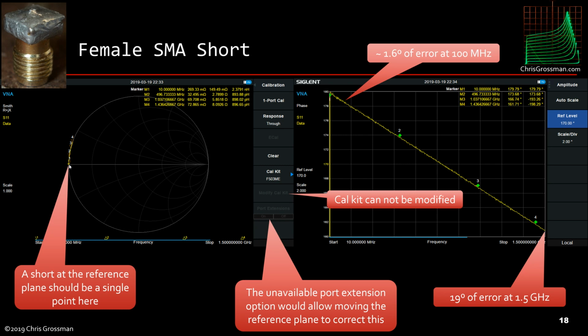done the calibration. If you notice here, for the short, the calibration should just be a spot here on the left portion of the Smith chart, but it's not. It starts here at 10 megahertz and rotates around as the frequency changes. So now if I plot the phase of that versus frequency, we can see it's pretty much a straight line. So it's basically just a time offset error. And for the short cal, I've got 19 degrees of error at 1.5 gigahertz.